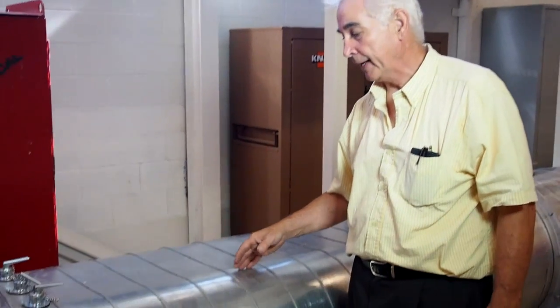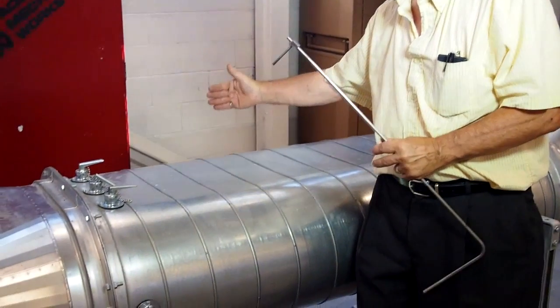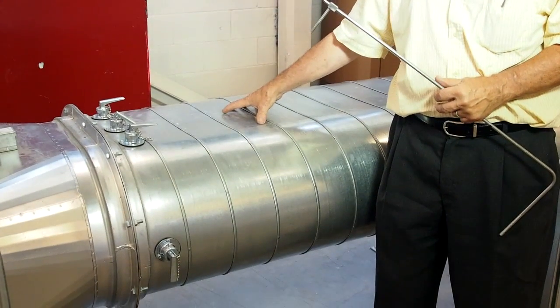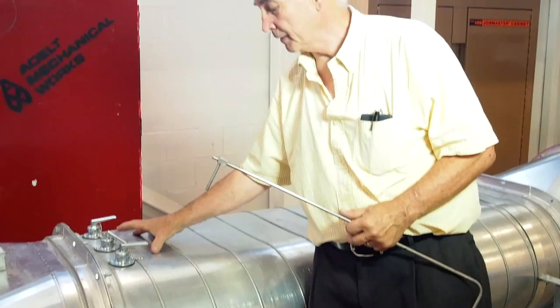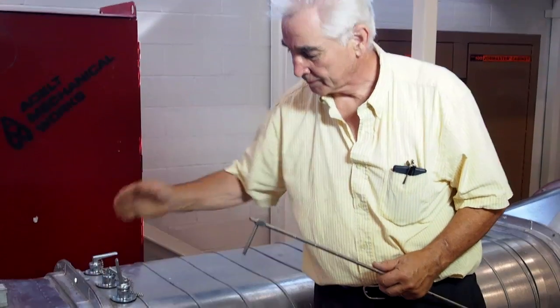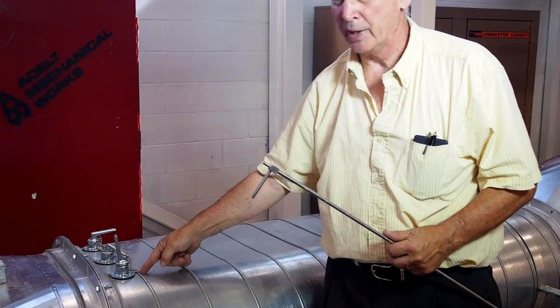Now we have an oval duct. There are very many people using oval duct, but if you come across an oval duct, just consider it as two halves of a round duct with a piece of rectangular duct between. So, we have the holes for the rectangular duct, and this hole also serves as one of the diameters for the round duct.